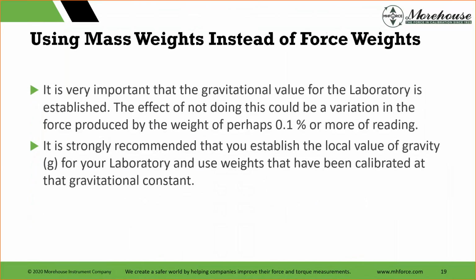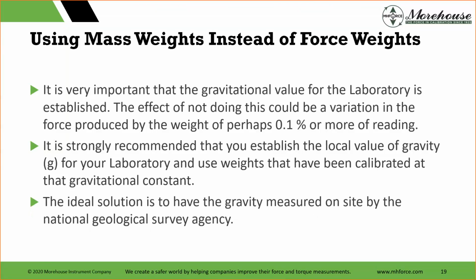One easy error is using mass weights instead of force weights. And it is very important that the gravitational value for the calibration laboratory is established. The effect of not doing this could be a variation in the force produced by weight of perhaps 0.1% or more of reading. So it is strongly recommended that you establish the local value of gravity for your laboratory and use weights that have been calibrated at that gravitational constant. The thing here is, if you're using mass weights, they're not adjusted for gravity. They're not adjusted for air buoyancy, and they're not adjusted for air density. So you really need to correct them for force.